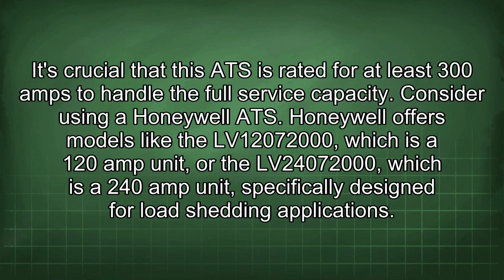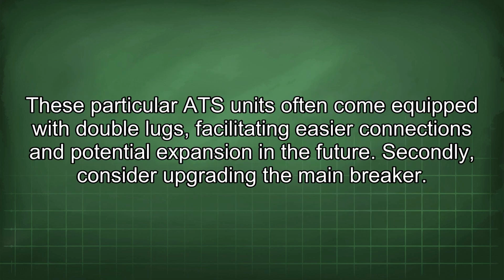Consider using a Honeywell ATS. Honeywell offers models like the LV12072000, which is a 120 amp unit, or the LV24072000, which is a 240 amp unit specifically designed for load shedding application. These particular ATS units often come equipped with double lugs, facilitating easier connections and potential expansion in the future. Secondly, consider upgrading the main breaker.